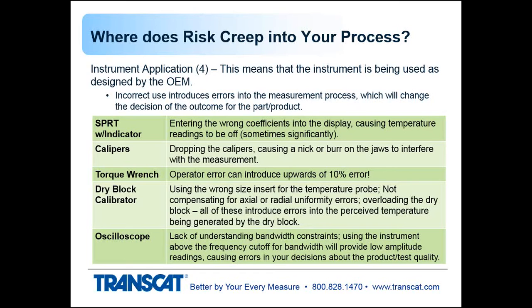Dry block calibrators or dry wells: using the wrong size insert for the size of the temperature probe is obviously going to give some cooling and not going to transfer the heat as uniformly as it should. There are axial and radial uniformities. Radial uniformity is from well to well, one point to another, and axial uniformity is top to bottom in the well. Overloading the block with too many probes inserted can also cool it off and cause errors. So the use of the instrument is critical to maintaining good measurement.